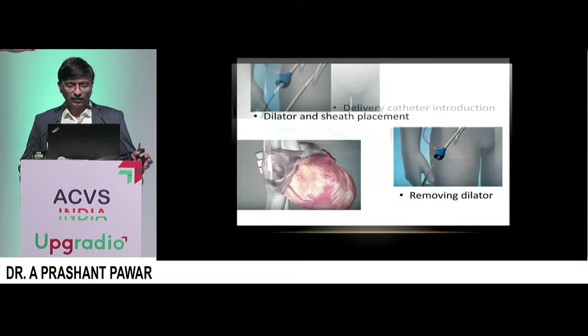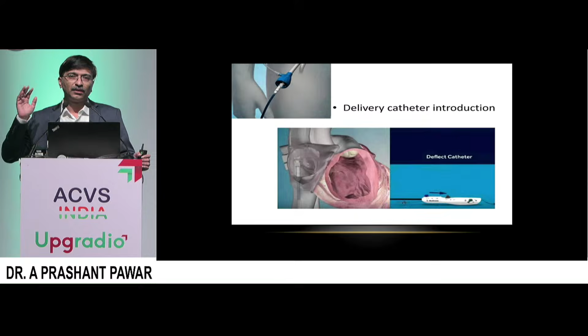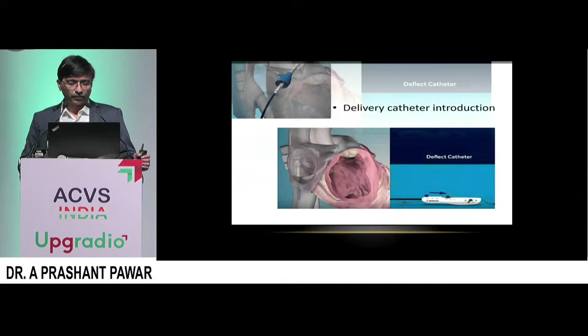So you have this dedicated catheter which comes from Micra. It has 3 buttons on it. The blue button is for releasing, for advancing the device. There is a gray color button which is a deflection button. So in the initial phases, what all complication occurs is because of erroneously too hard deflecting. This is very sensitive button. If you deflect even minimal 1 mm, it deflects rapidly. Third is this lock.